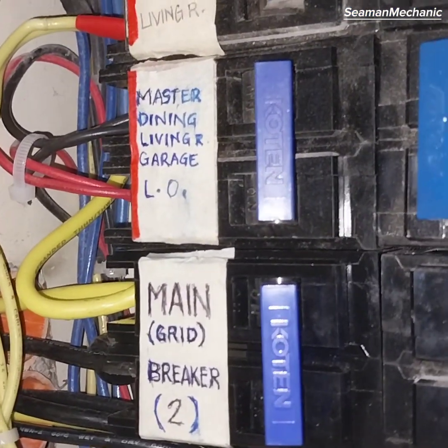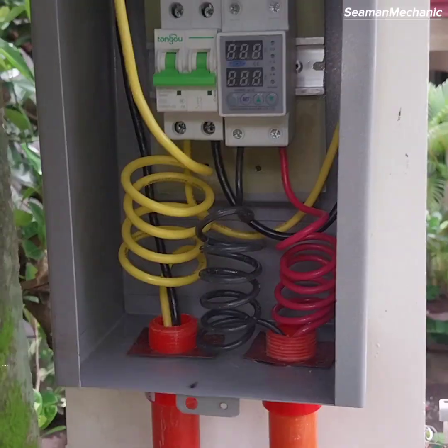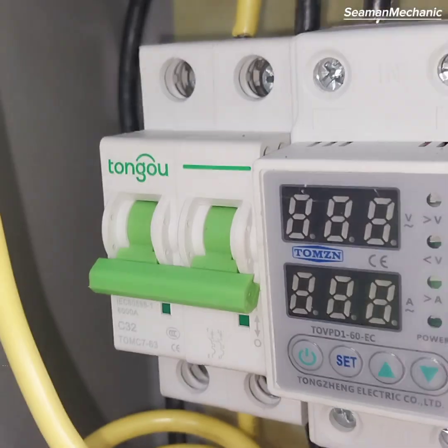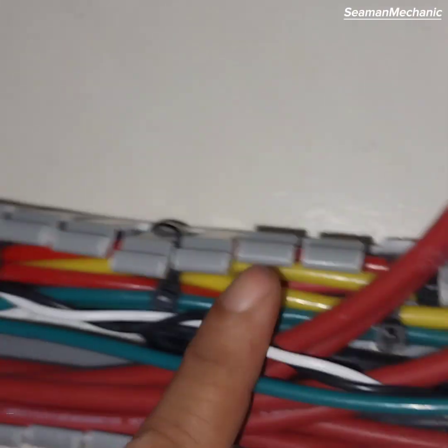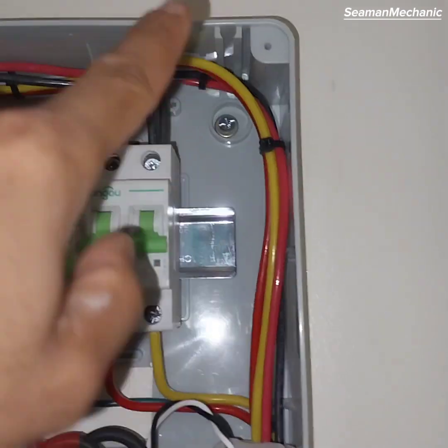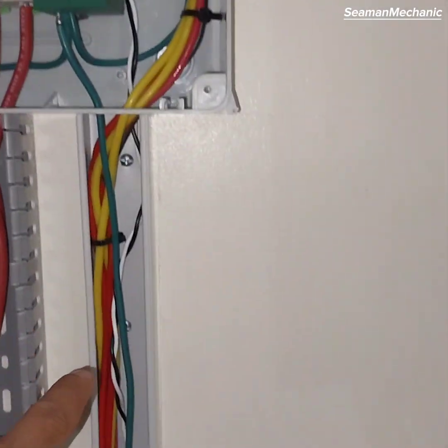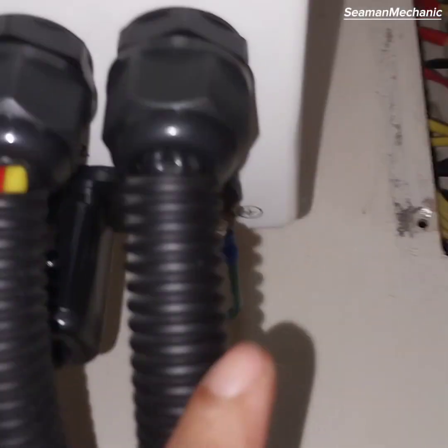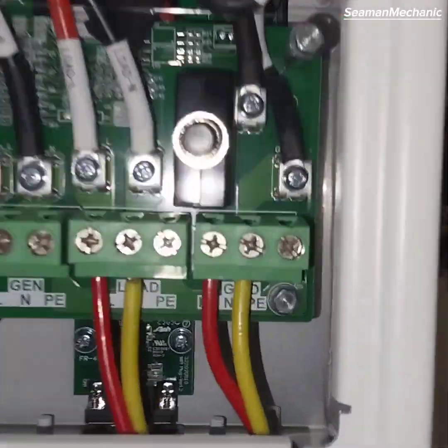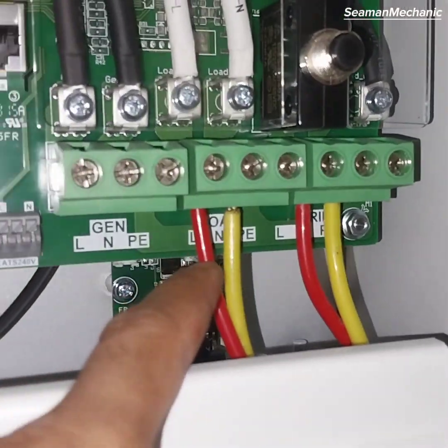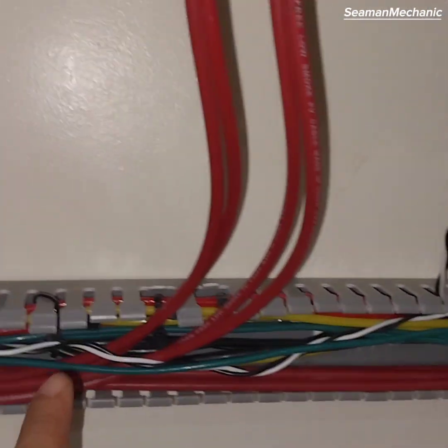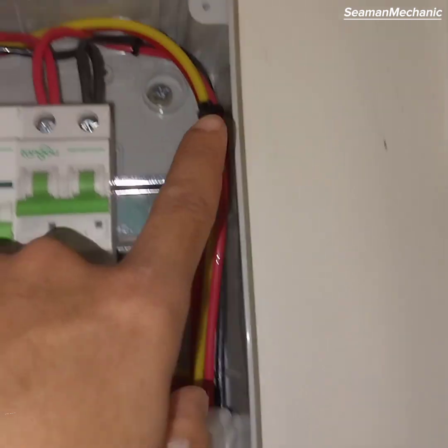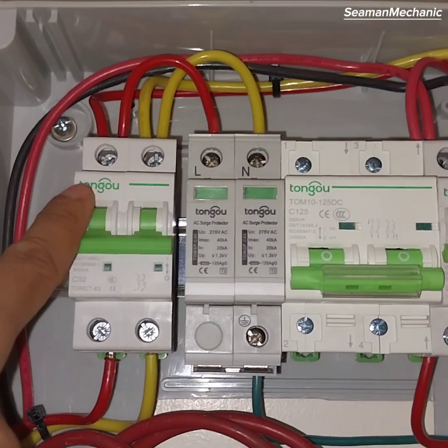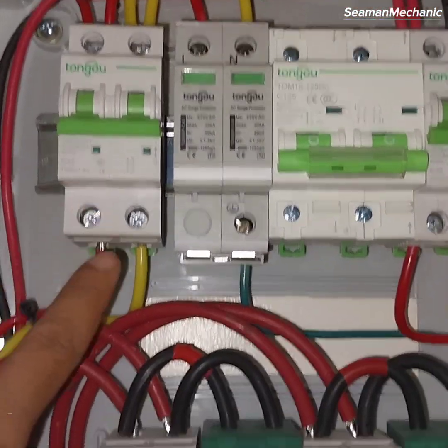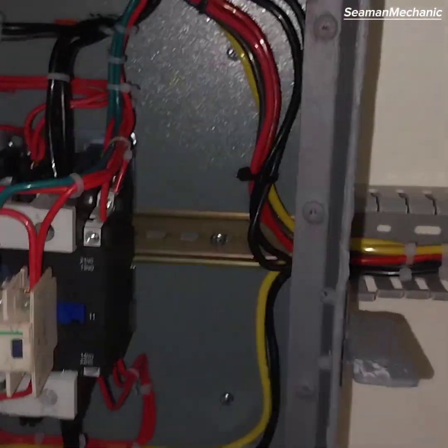From grid line, it goes into DU box, then to AC circuit breaker and adjustable voltage and current protective device. From DU box, AC surge protection device to AC circuit breaker inverter in. Then from AC circuit breaker, it goes to inverter grid in. From inverter loadout or AC out, it goes to inverter AC or loadout circuit breaker and connected parallel to AC surge protection device. Then goes to AC out adjustable voltage and current protective device.